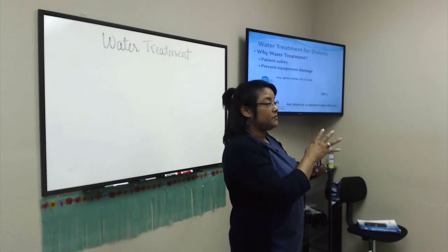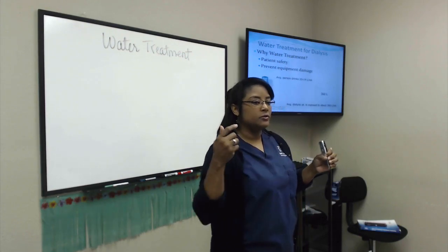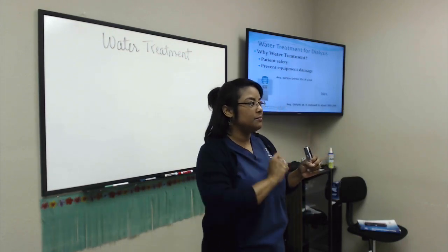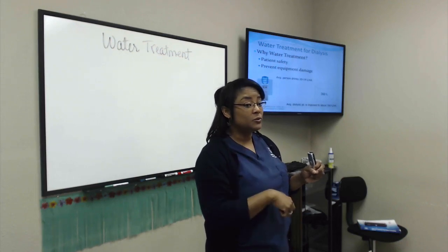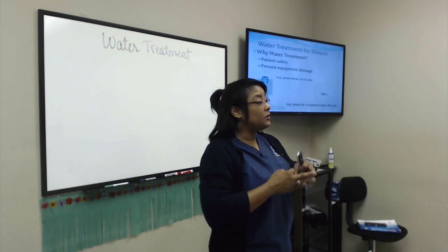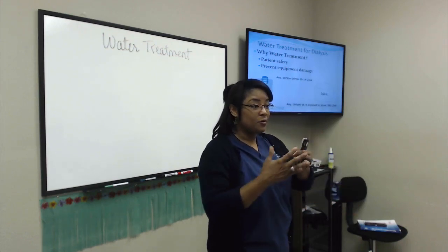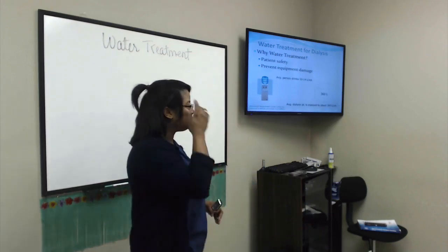And in that type of dialysis, the patient uses a certain amount of liters per treatment. So let's say that the patient uses 20 liters of dialysate. 60 liters will be enough for 3 treatments, okay? And they don't have to turn on the water for those 3 days. Does that make sense? So we're not too far from it.